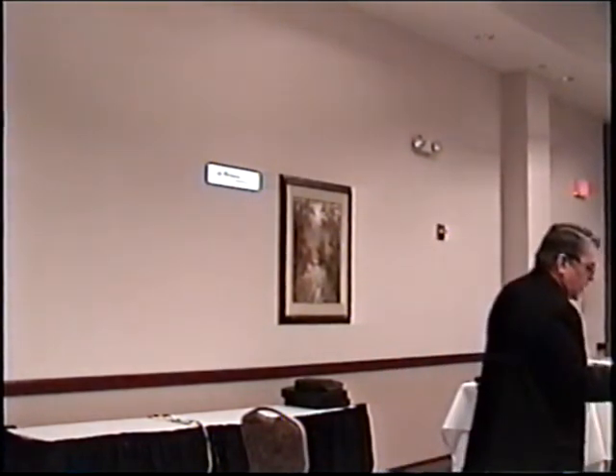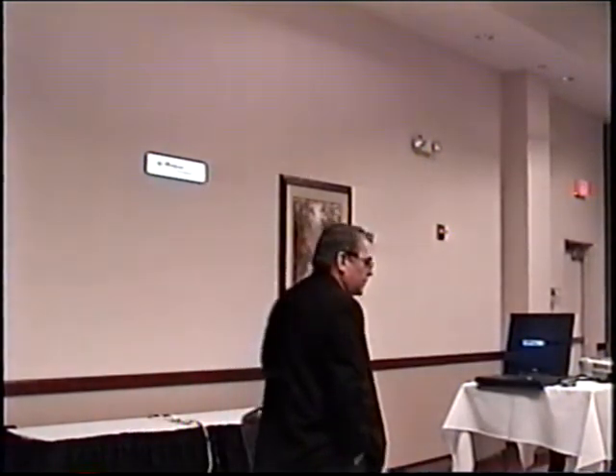Water mist systems come in low pressure, intermediate pressure, and high pressure. Low pressure, Securiplex, for example, was a low-pressure twin fluid system. Can get excellent atomization. Had its own problems with having to provide air and water and whatnot. Generally, you find with the Tyco systems, you kind of get up into that intermediate pressure above 200 psi, 200 to 500 psi, and even some of these you'd call a spraying systems company single orifice spray nozzle that Jerry Back used in machinery space tests and Coast Guard testing. It's just a single orifice, nothing fancy, kind of good around 200 psi.